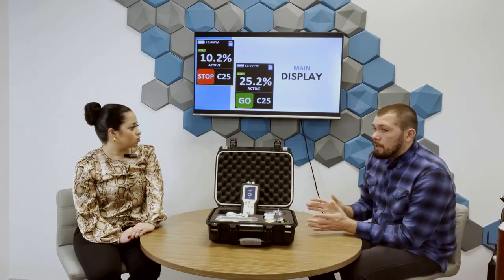If you want to make some changes to your device in operation, or you want to select a different blend, you can enter the menu, right? From here you can update your date and time. You can change your data logging interval. So let's say you want more or less data while you're sampling, you can change that number. You can make some adjustments to the backlight and power saving mode. That way it may be a little bit easier to read if you're in a darker setting, or you want to preserve your battery for a little bit longer battery life, things like that. Then you can go ahead and do your blend selection, pick a different CO2 blend.